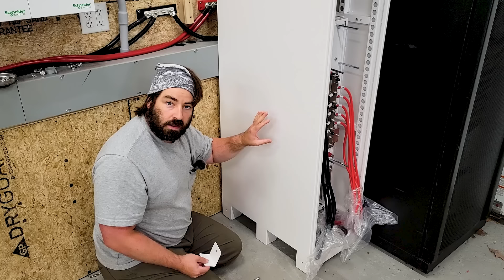Inside the cabinet came packaged some of these steel L feet. And they go on here and they allow you to bolt it to the floor, which would be important if you're in a seismic zone. So I'm just going to bolt them on so that there's just a little bit more stability to the cabinet, but I'm not worried about drilling into this floor. Also, this is a radiant floor with hydronic tubing going through it, so I really don't want to mess that up. The cabinet's in place and it's looking good. At this point, I'm going to remove the bus bars and the wiring. That's going to free up the space to get the batteries in and do my knockout.